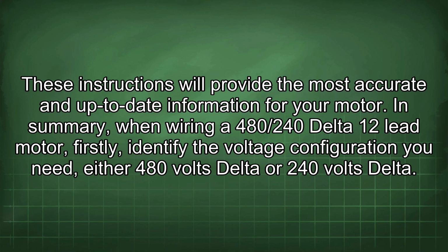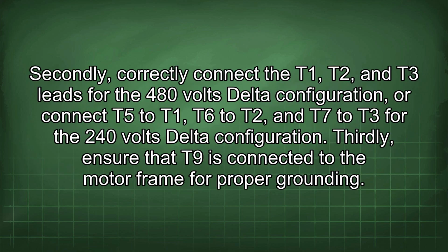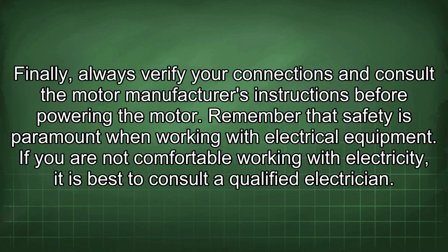In summary, when wiring a 480/240 delta 12 lead motor, firstly, identify the voltage configuration you need, either 480 volts delta or 240 volts delta. Secondly, correctly connect the T1, T2 and T3 leads for the 480 volts delta configuration, or connect T4 to T1, T5 to T2, and T6 to T3 for the 240 volts delta configuration. Thirdly, ensure that T9 is connected to the motor frame for proper grounding. Finally, always verify your connections and consult the motor manufacturer's instructions before powering the motor.